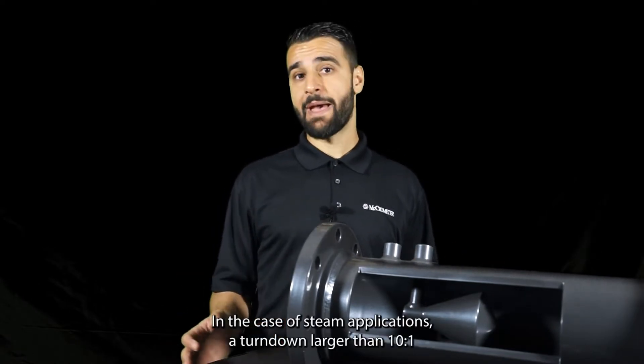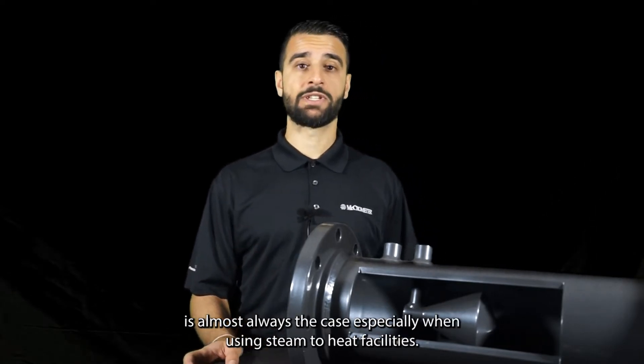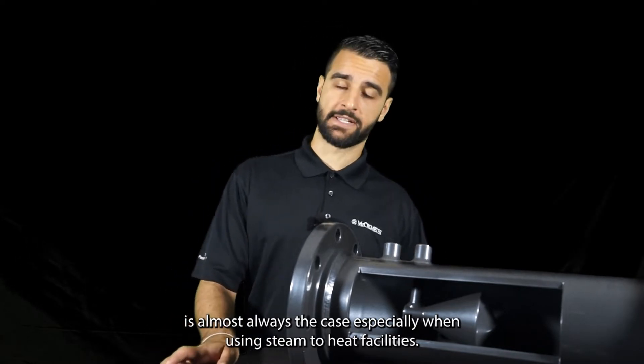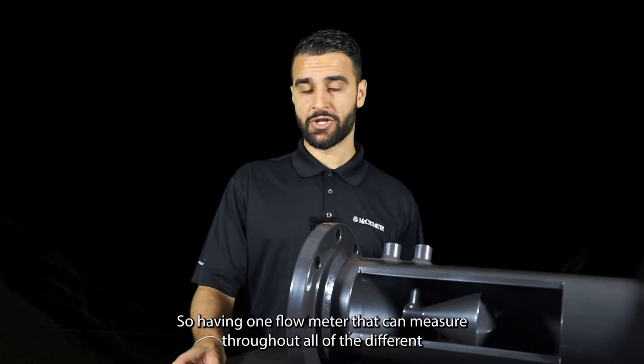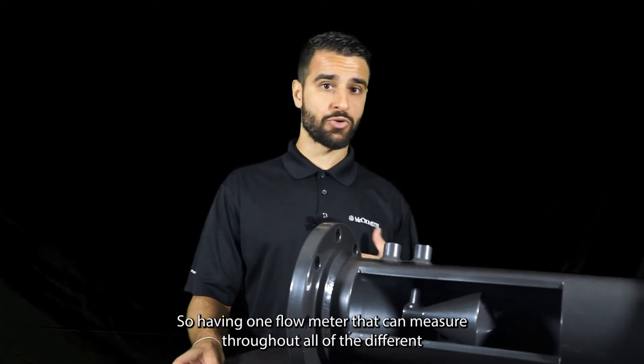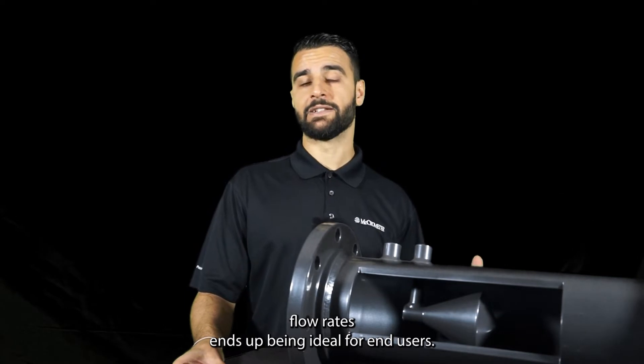In the case of steam applications, a turndown larger than 10 to 1 is almost always the case, especially when using steam to heat facilities. You're using a lot of steam in the winter and very little in the summer, so having one flow meter that can measure throughout all of the different flow rates ends up being ideal for end users.